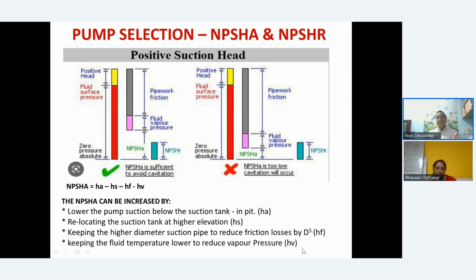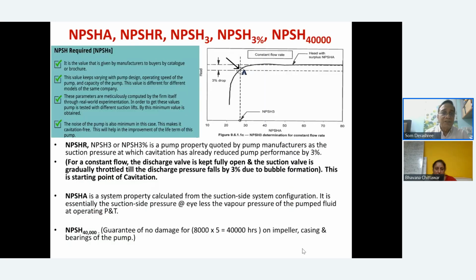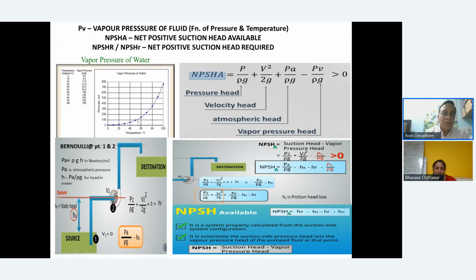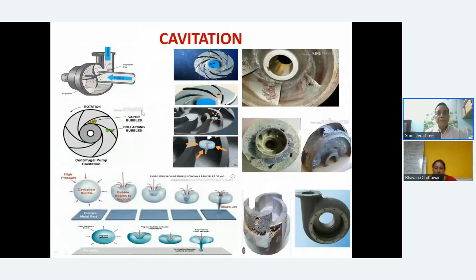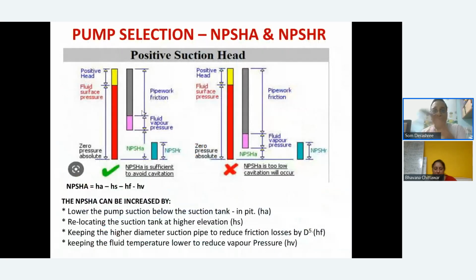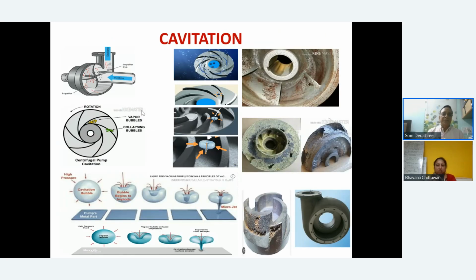Okay, there's another case where you cannot do anything. It's a fait accompli for you. Then, if you can, maybe reduce the vapor pressure by lowering the temperature, because as the temperature goes down, vapor pressure also goes down. Okay. So with this, we have understood what NPSH A, NPSH R, NPSH 3, NPSH 40,000, NPSH 3% are, and what the implication is. Now let's see how the cavitation happens.